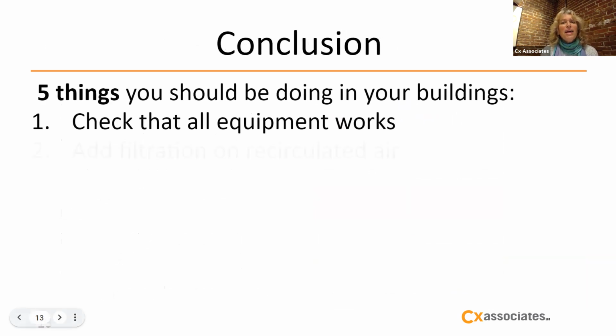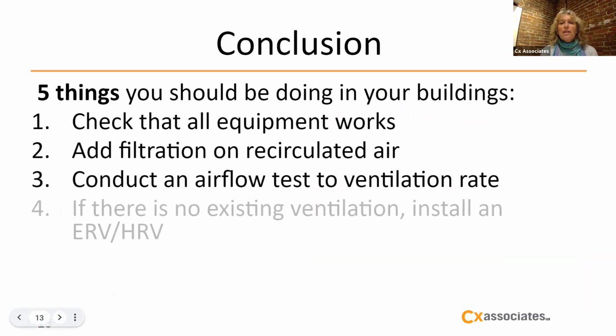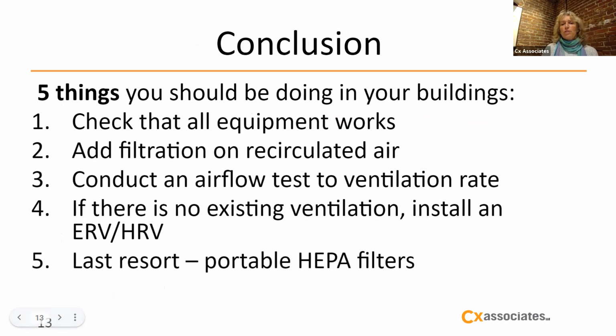Thank you, Chanel. So, the 5 things you should do in your buildings. Start by making sure that all the equipment works. If you have a ventilation system, an air handling unit that has outside air, make sure that the damper opens, make sure that the fan works, and make sure that the temperature sensors work, so that you know what you have.